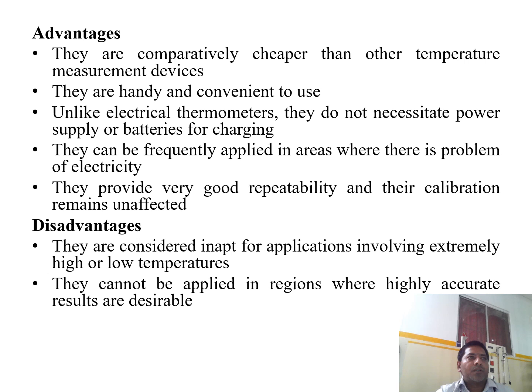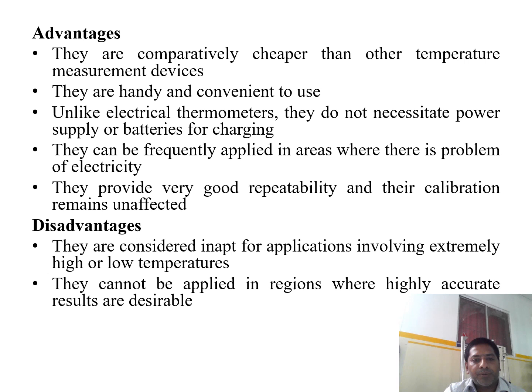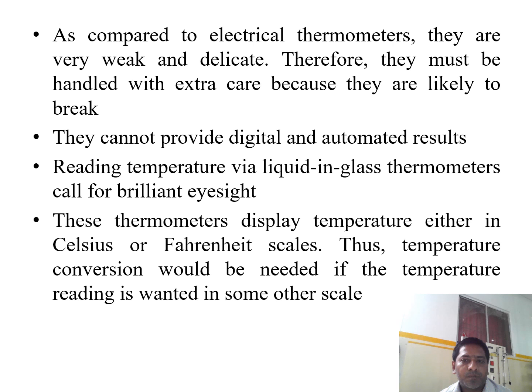The advantages of liquid-in-glass thermometers: they are comparatively cheaper than other temperature measuring devices, handy and convenient to use. Unlike electrical thermometers, they do not require a power supply or batteries, so they can be used in areas where there is a problem with electricity. They provide very good repeatability and their calibration remains unaffected. Disadvantages: they cannot be applied in extreme high or low temperature applications, nor in regions where highly accurate results are needed due to possible oscillation of plus or minus. Compared to electrical thermometers, they are very weak and delicate and must be handled with extra care as they are likely to break.